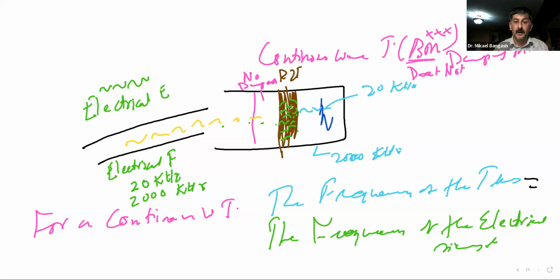We still talk about sound waves, mainly because this transducer doesn't have a backing material, or damping material. The vibration produced by each wave of the electrical signal is not going to be damped down. Which mainly means that if it is hit by a frequency of 20,000 cycles per second, it is going to vibrate 20,000 times per second, which will produce a wave with a frequency of 20,000 cycles per second. That becomes the frequency of this transducer here.